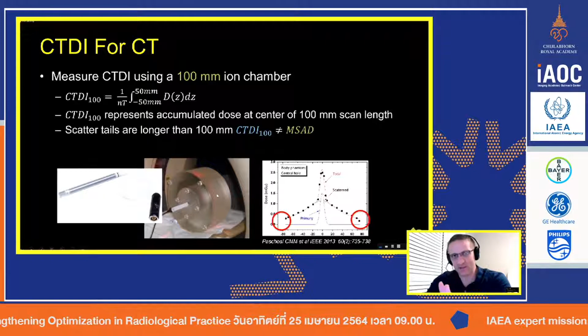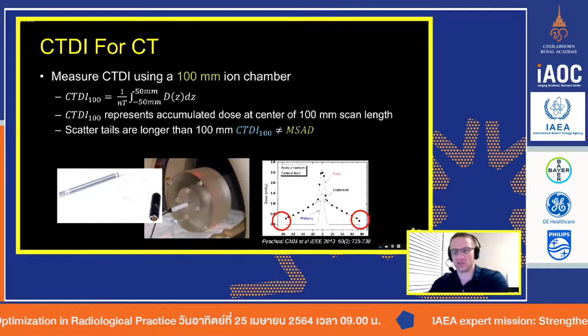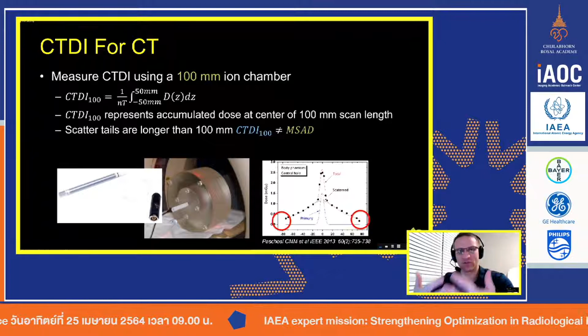Now think about that on a fluoro unit. We're not doing 4 centimeter imaging on fluoro. We have these 25 or 30 centimeter, even 40 centimeter fields, depending on the detector size you've got. And so one of these phantoms being 15 centimeters is not even nearly as good at collecting all of the scatter and doing an actual dose calculation for the dose to the area of a fluoroscopic spin.